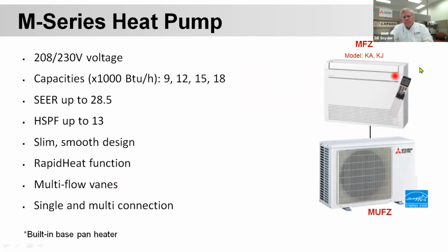Very smooth design. This could be partially recessed into the wall if it was new construction, or it can be mounted right on the wall. And it mounts above the floor. You need a few inches under it. So this mounts on the wall. It could be mounted on the floor. If you're going to take your refrigerant lines down through the floor, that could be done. It can be done both sides. The refrigerant lines can come out this side or the other side or down. You've got lots of options on this, but typically it hangs above the floor by about 4 inches. You drill a hole in this lower right-hand corner and your refrigerant lines go out there. Refrigerant lines, your electrical, and your condensate all go out the same hole.